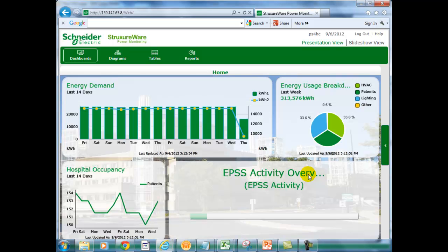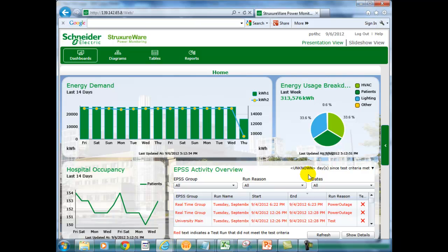A best-of-class power monitoring system like StruxureWare Power Monitoring provides great value through energy dashboards, power quality widgets, etc. But segment-specific applications like EPSS bring so much more to the table. Critical facilities often have no easy way to prove whether their emergency systems will work reliably in the event of an outage. Generators and transfer switches have the nasty habit of malfunctioning exactly at the wrong time. Stuck transfer switches, faulty generator controls, the list just goes on.